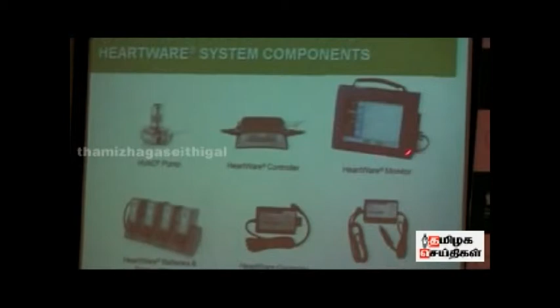This is the monitor. With this you can actually control the pump speed. By increasing the pump speed, you can increase the flow. Then these are the batteries which need to be charged, and the batteries will last for 12 hours, and these are the charging cables. This is how it looks once the device is attached to the heart.